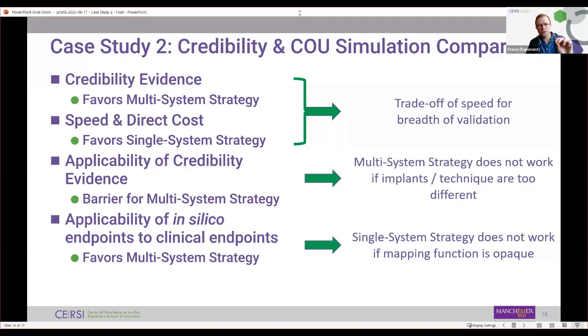The applicability point, this middle one here on the right-hand side, is incredibly important. Using the predicate sounds great if the factors that you're including in the predicate as they relate to the clinical consequences are also applicable for the new design, right? So with respect to micromotion, with respect to loosening, the way in which you treat the contact, for instance, between the tray and the bone needs to be appropriate for both devices. If it's only appropriate for the predicate, then it doesn't do you any benefit for the new system, etc. So applicability is incredibly important for the multi-system strategy.